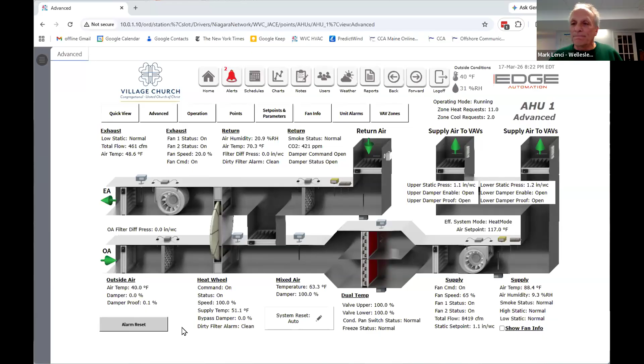If something broke, and we've only had one thing break, and that was the power supply to one of these variable frequency fans in the roof, obviously we can't replace that from home. You have to have a tech, and when the fan's off and it won't restart with this, then the technician's got to go up into the building and find out what's going on. And we did have that happen once.